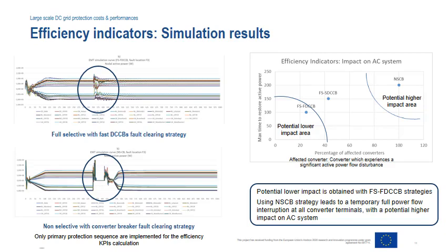With a fully selective strategy, only a part of the converter terminals experiences a significant temporary power flow disturbance, if a relevant control tuning of MMC converters is implemented. With a non-selective strategy, all converter terminals see a temporary full power flow interruption. The potential impact on AC system stability can be projected by positioning the different protection strategies, considering on one side the percentage of converters seeing a significant temporary power flow disturbance, and on the other side the maximum time needed to restore active power, calculated among all simulated fault scenarios, as depicted in the figure on the right.